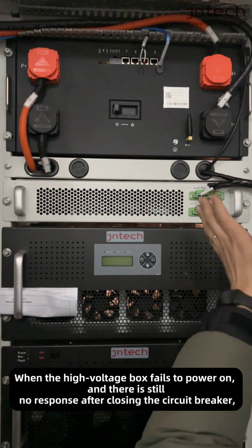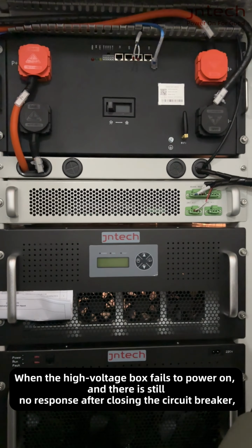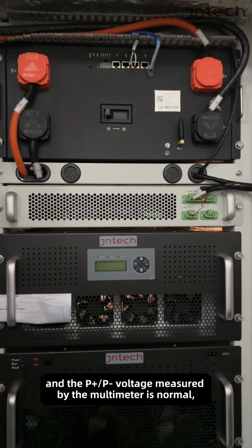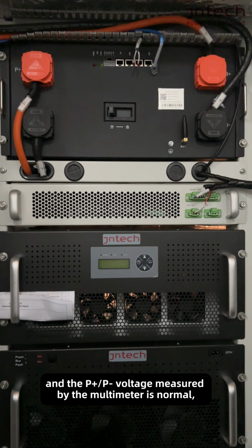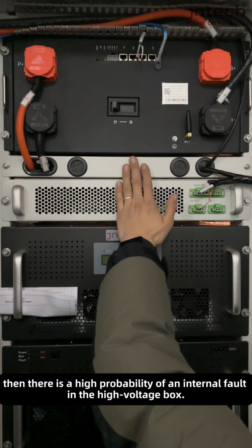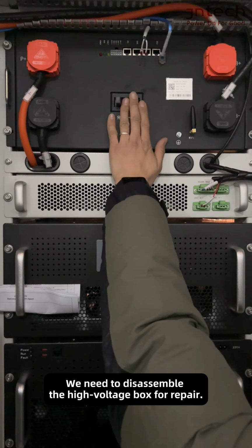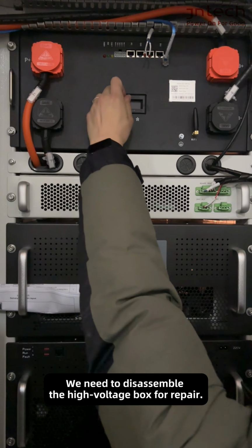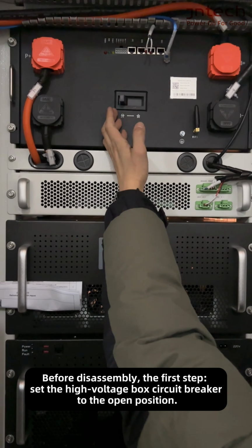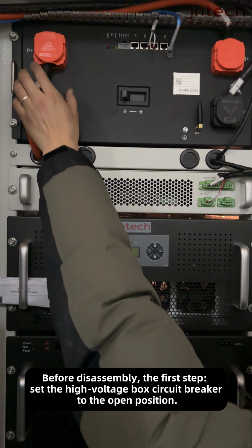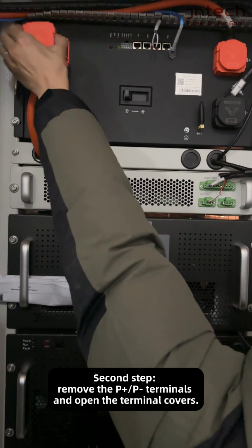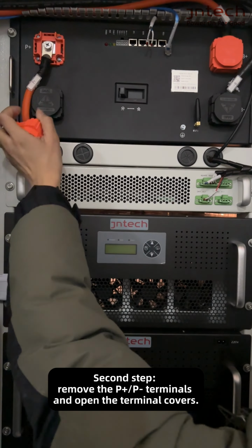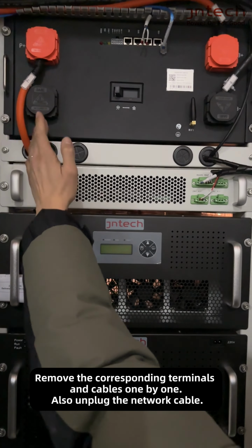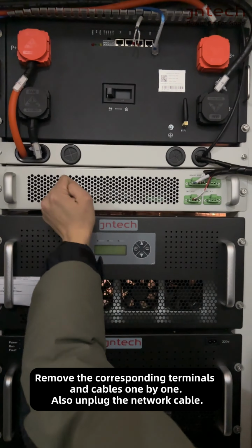When the high voltage box fails to power on, and there is still no response after closing the circuit breaker, and the P+/P- voltage measured by the multimeter is normal, then there is a high probability of an internal fault in the high voltage box. We need to disassemble the high voltage box for repair. Before disassembly, the first step, set the high voltage box circuit breaker to the open position. Second step, remove the P+/P- terminals and open the terminal covers. Remove the corresponding terminals and cables one by one. Also unplug the network cable.